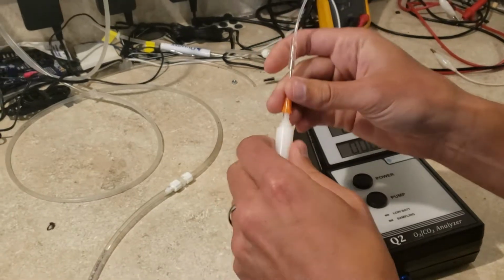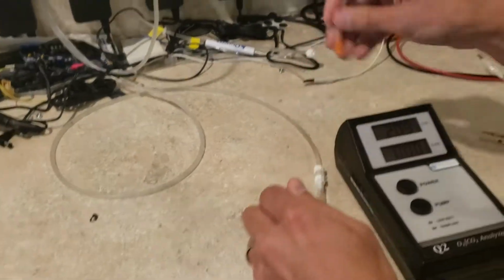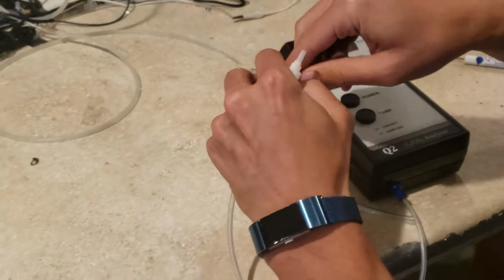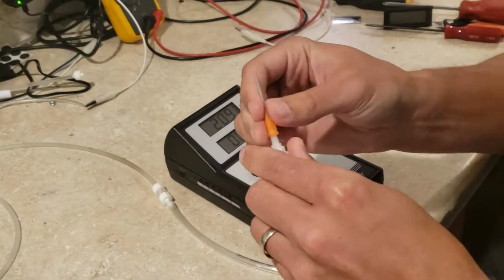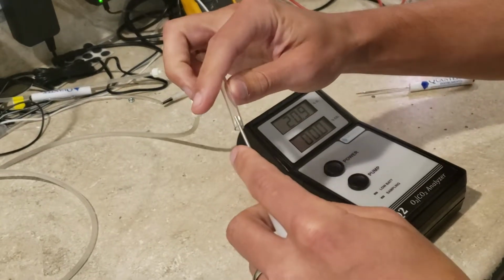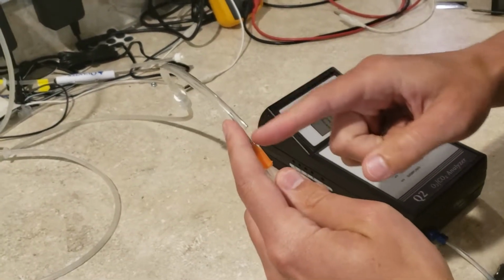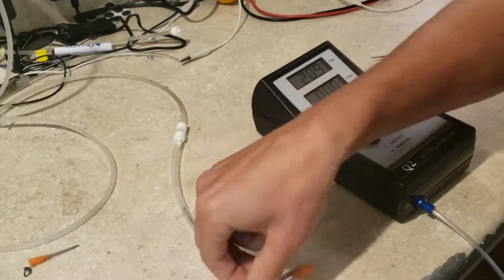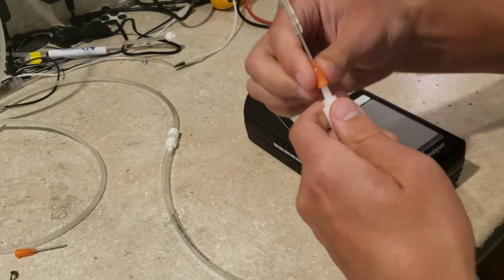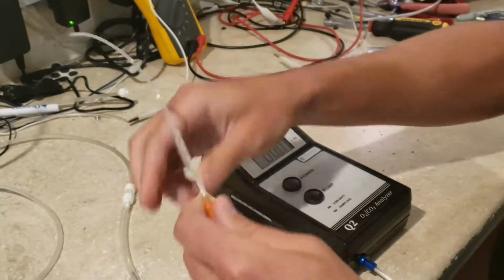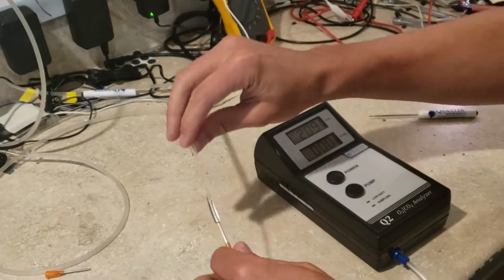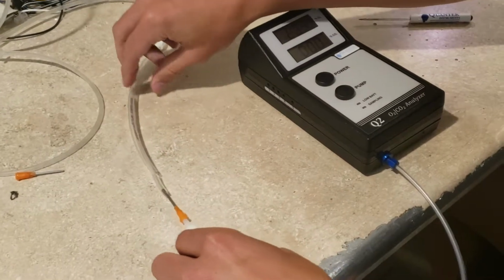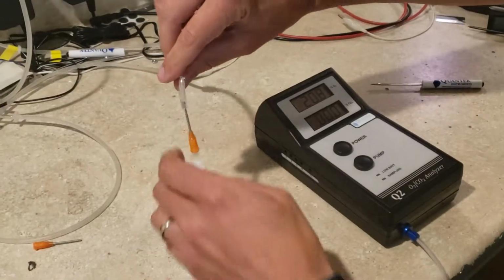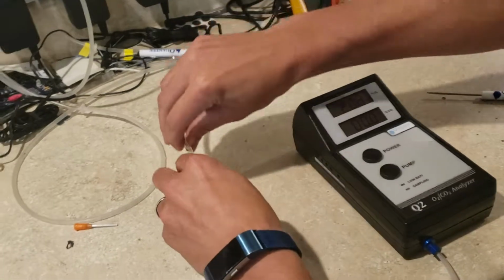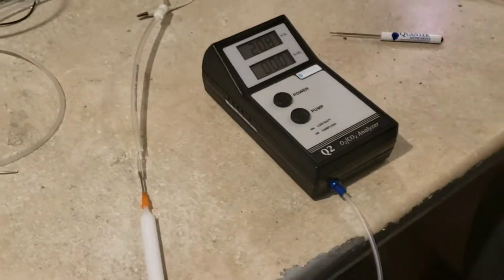It's very important to use something like this, because if you were to use, for example, just a needle like this that doesn't have any tubing connected to it, what's going to happen is when you go to put this in the calibration tube, you risk getting some room air sucked inside the needle. So with a longer piece of tubing like this, we can connect here and make sure that that connection is snug, and then we can really put it far inside the calibration tube here, without creating a firm seal, because of course if you were to connect these together and create a seal there, you would risk pressurizing the sensor, which you don't want to do.